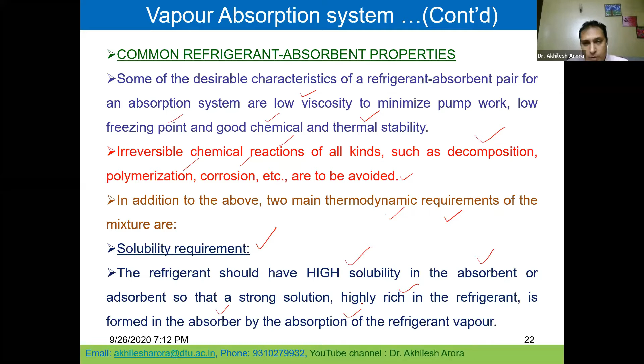In addition to above, two main thermodynamic requirements. What are the two thermodynamic requirements? This is very, very important. The first one is the solubility requirement. The refrigerant should have high solubility in the absorbent. This is required in the absorber section, so that highly rich refrigerant is formed in the absorber by the absorption of the refrigerant vapor. So we want that strong solution should be formed in the absorber.